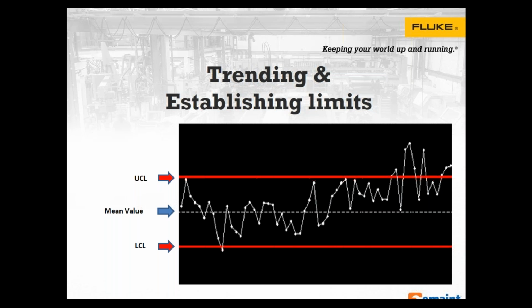We can see right here an example where these control limits are established by the program based on the performance of the asset. But again, I had to tell the program that this is a normal operating condition. You can see right there that we're starting to trend in a certain direction.